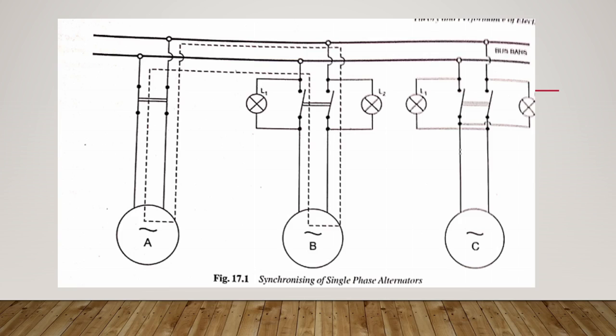Equality of the terminal voltages can be determined by connecting a voltmeter first to the running alternator or bus bars and then to the incoming alternator. The remaining two conditions, that is equality of frequency and phasing out, can be determined with the help of two lamps which are connected across the ends of the double pole paralleling switch, and these are known as synchronizing lamps.